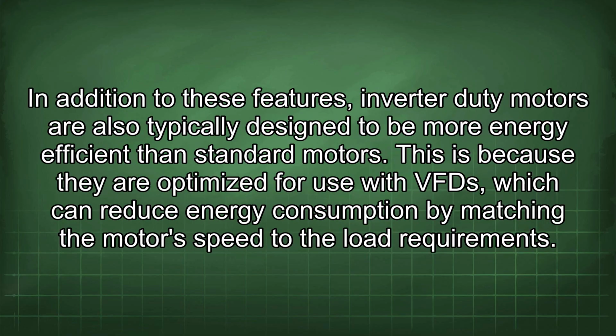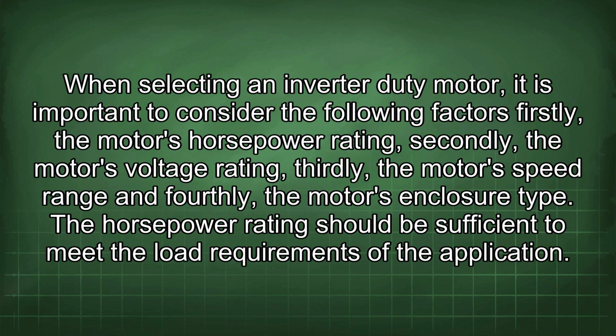In addition to these features, inverter duty motors are also typically designed to be more energy efficient than standard motors. This is because they are optimized for use with VFD, which can reduce energy consumption by matching the motor's speed to the load requirements. When selecting an inverter duty motor, it is important to consider the following factors. Firstly, the motor's horsepower rating. Secondly, the motor's voltage rating. Thirdly, the motor's speed range. And fourthly, the motor's enclosure type.